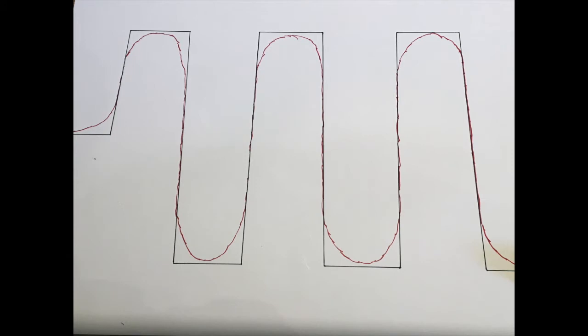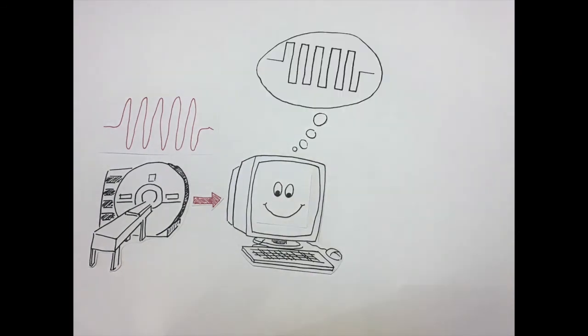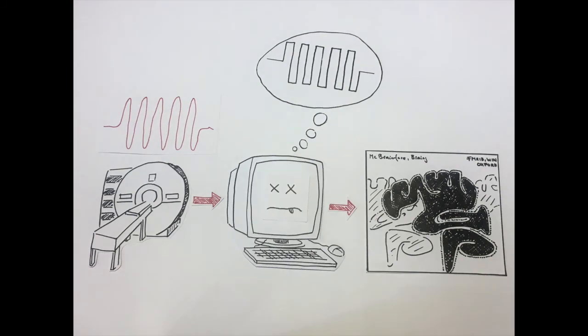Once the gradient gets to the end of the trajectory, the data is fed to the image reconstruction computer as shown before. But the fact that the gradient did not follow the trajectory it should have can have pretty big consequences.